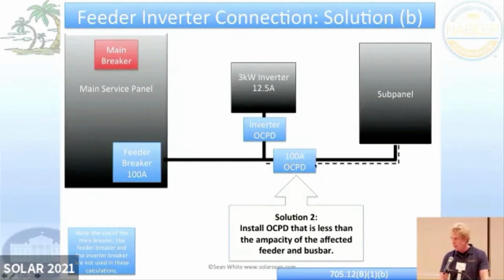You apply the tap rule, the solar tap rules that we're going to look at in a little bit. And so what it comes down to is that there's this thing called the 25-foot tap rule. And so if you're within 25 feet of this connection over to here, you can put that 100 amp breaker in the sub panel. But if it's greater than 25 foot, then if you had a really smart inspector giving you a hard time, they were not going to let you put it in the sub panel.